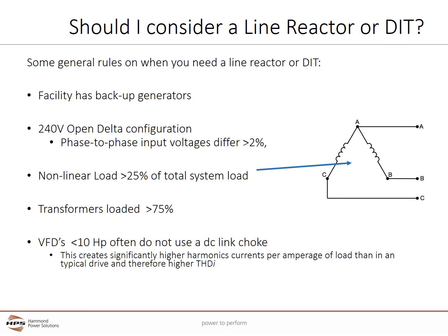Here are some general rules on when you need to consider a line reactor or a DIT. Backup generators have to be sized to supply not only the motor load, but the additional current harmonics. Reducing current harmonics, as line reactors and DITs do, may reduce the load enough to allow the sizing of a smaller, less expensive generator. 240 volt open delta circuits are often associated with phase-to-phase voltage differences, which can cause current unbalance on the VFD's rectifier circuits. Note, phase unbalances can occur in any type of system configuration, but they are most prevalent in 240 volt open delta configurations, which are usually found in rural areas or older parts of the electrical grid.